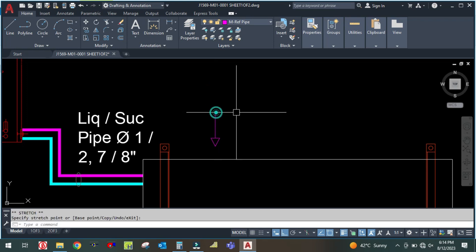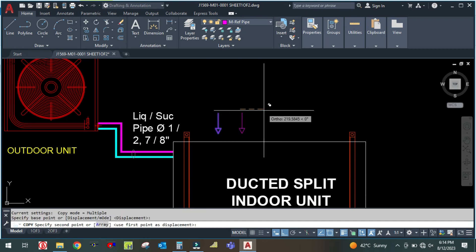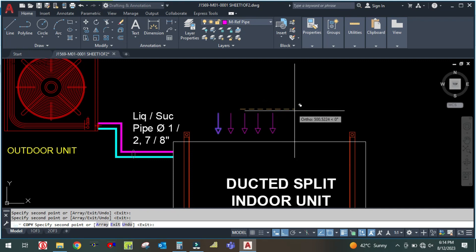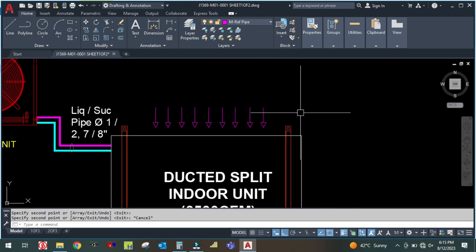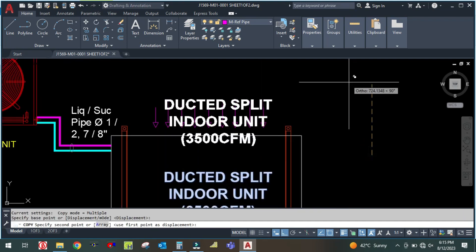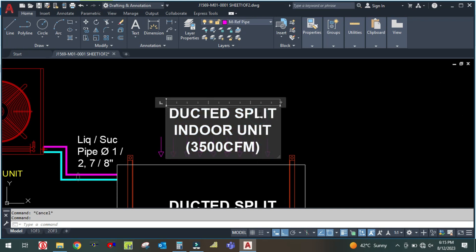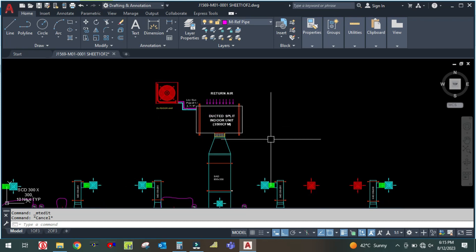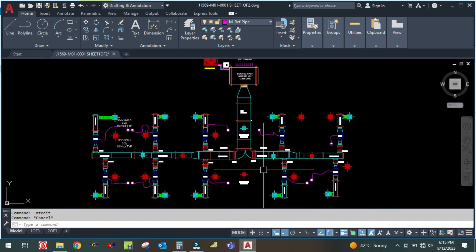This is how this HVAC design drawing looks. It is a very simple design but very informative for beginners as well as experienced people, because the concept is very clear. At the end of each branch you can see a VCD — volume control damper — which is used to control the airflow of each space. The green color represents flexible connections — from the duct to each diffuser there is a flexible duct connection.